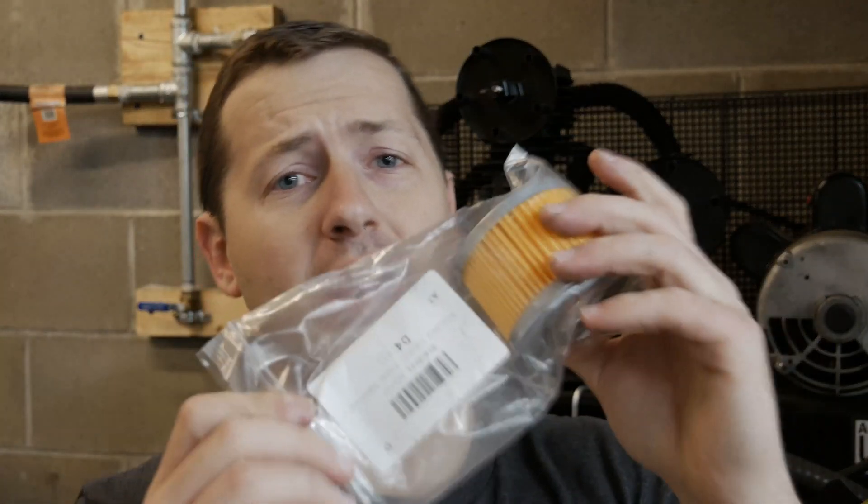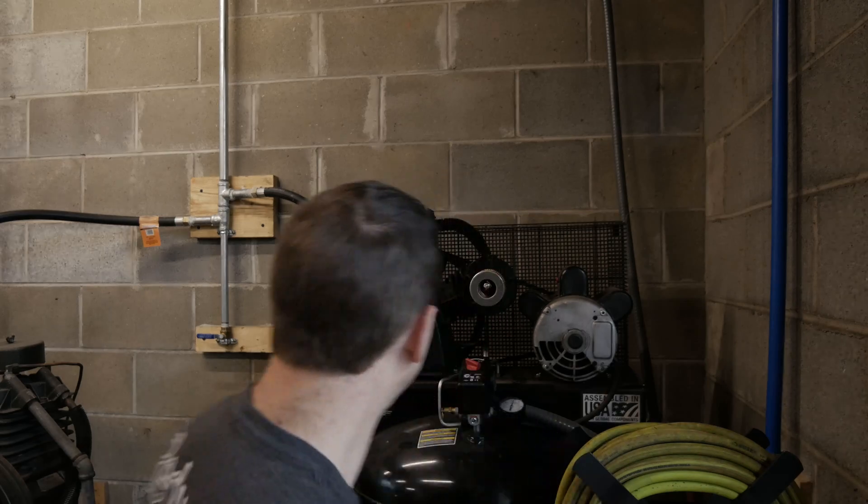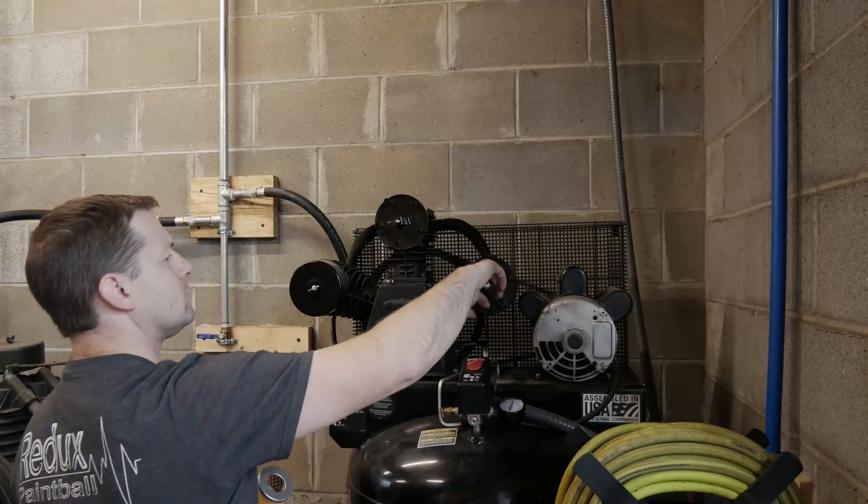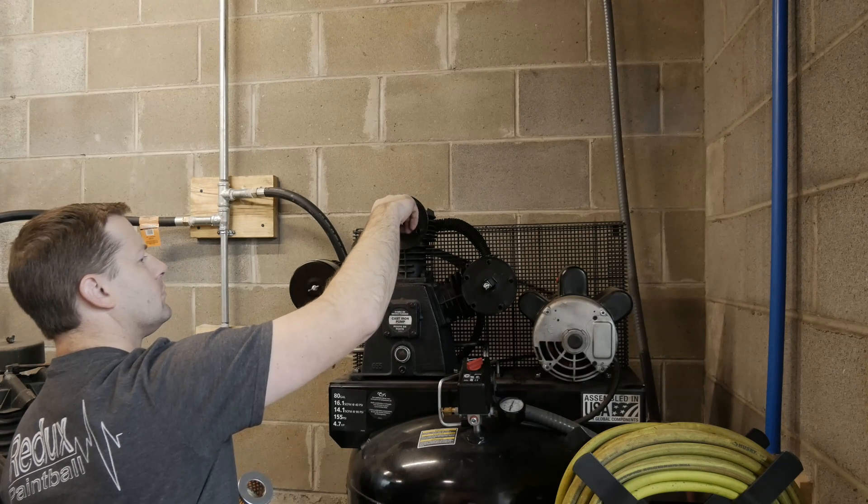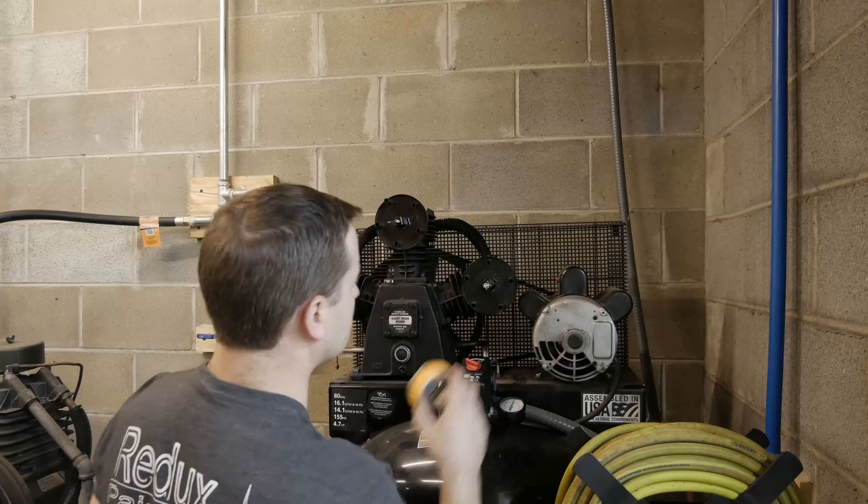While we're busy doing a little bit of maintenance on it, I went ahead since I had to order a gasket anyway and I ordered three new intake filters. Before I get all this closed up, I just want to make sure that that fix did actually correct the problem. So we're going to kick this thing on and make sure the intake is only doing what it's supposed to do, which is sucking air in. Success, and it was just that quick and just that easy. The gasket did fix the problem so now we're going to wrap this thing up and make sure she builds pressure all the way to 150 psi.